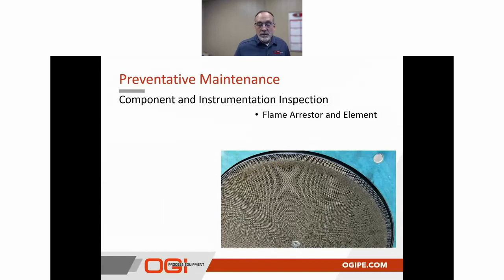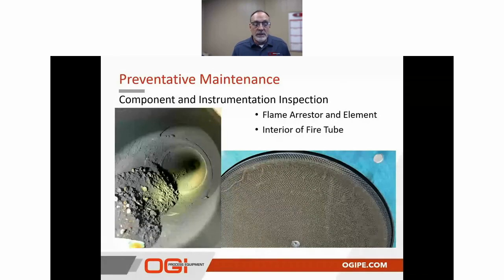In this case, we blew dry, high pressure air through the flame arrestor in the opposite direction of the normal airflow. And if you do use water or some kind of high pressure water wash, we encourage you to blow that out again with dry air. It ensures that the small openings within that element are free. The next thing we want to take a look at is to remove the hammerhead flange off the end of the stack and look through the combustion chamber to make sure that it's free of any kind of debris.